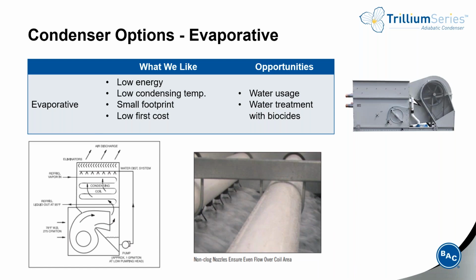Evaporative condensers work by spraying water directly on the heat exchanger, typically the refrigerant coil, but it could be a water coil in case of a fluid cooler application. Heat is removed as the spray water evaporates off of the heat exchanger. So the capacity available is based on wet bulb temperatures, not dry bulb temperatures. Wet bulb temperatures, you could think of it as a measure of the moisture content of the air. Wet bulb temperatures will always be lower than corresponding dry bulb temperatures.